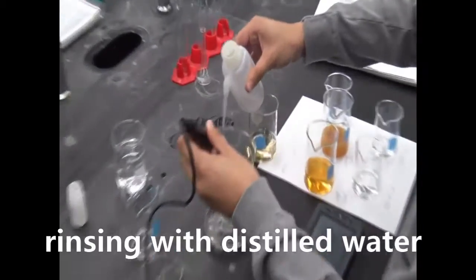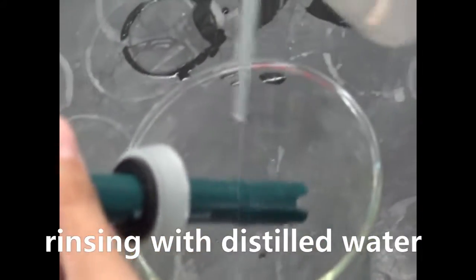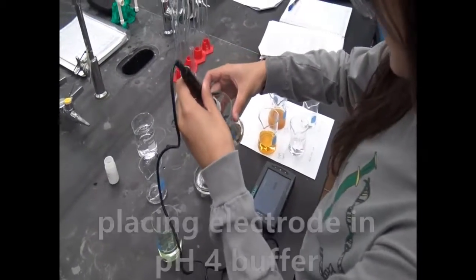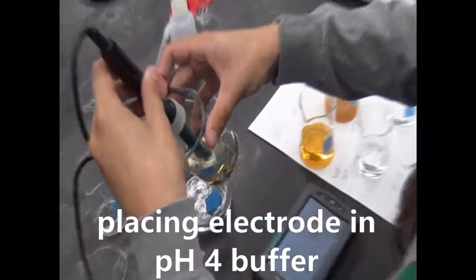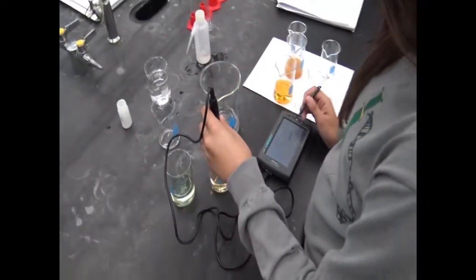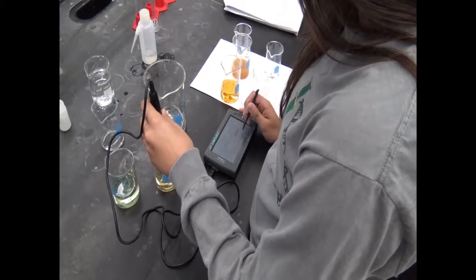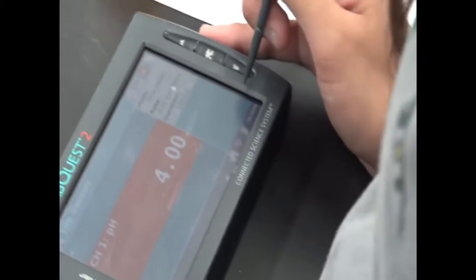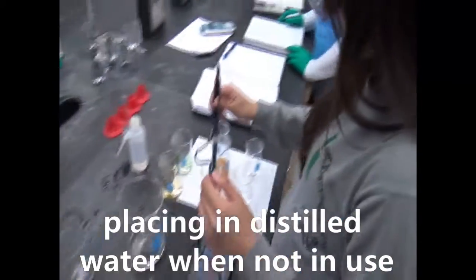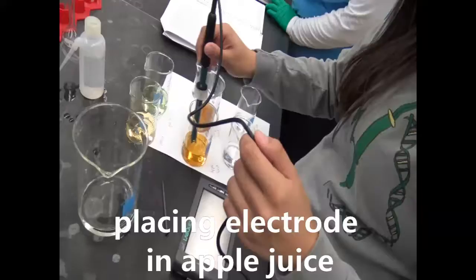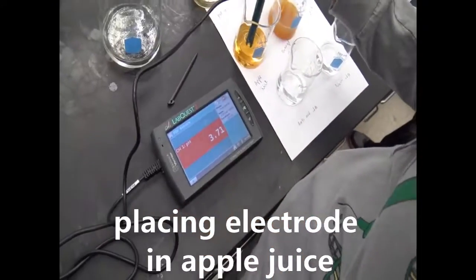Stick the probe into the solution and wait for the voltage to stabilize, then press keep on the meter screen. Once stabilized, remove the probe and rinse with distilled water. Rinse between every solution and replace the probe into a beaker containing distilled water when the meter is not in use. Continue by placing the probe into the second solution, pH 7 buffer in this instance. Input this number, then press OK and wait until the voltage stabilizes once again. Once it's stabilized, press keep on the meter and then press OK to finish the calibration.